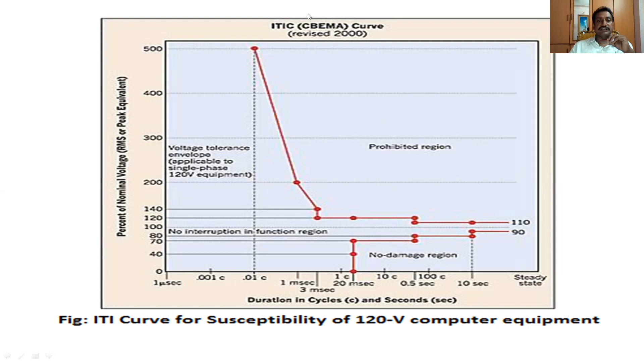Actually, the voltage tolerance envelope applies to single phase 120 volts. It is the no interruption in function region. So 90 to 110 is a safe region, and 120 is also a safe region. Below 90 is the no damage region, due to the low energy requirement. Above this region, 140 and above, is the prohibited region. In this region, due to short circuits or any malfunction of equipment, the computer may be damaged. So the CBEMA curve was revised by the ITIC curve in 2000.